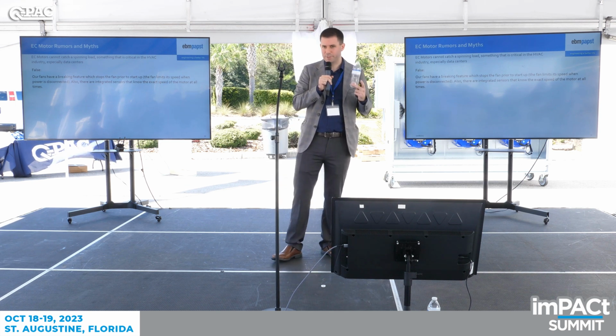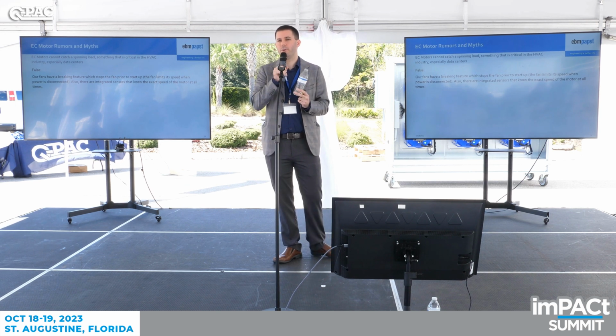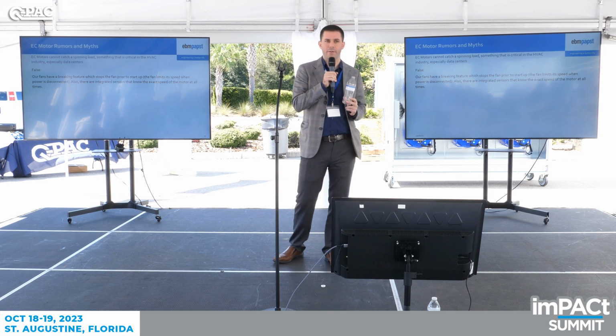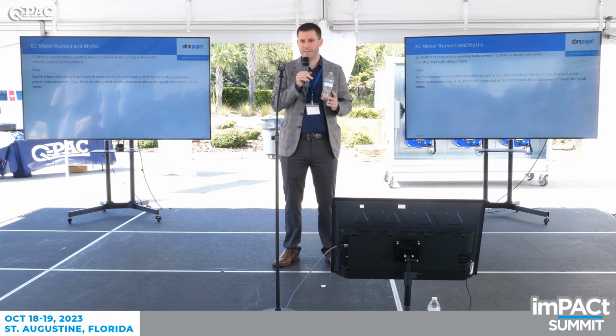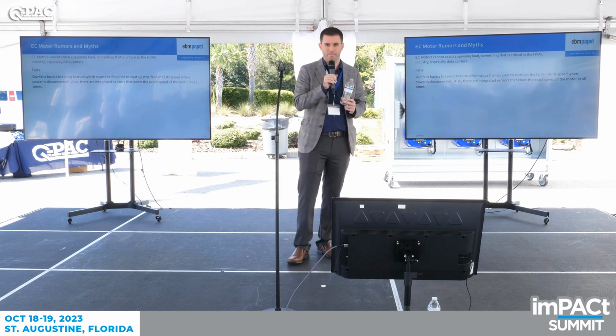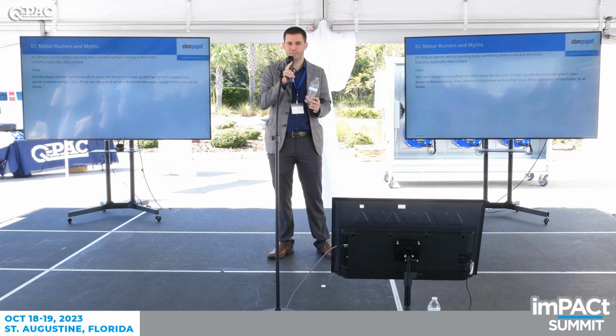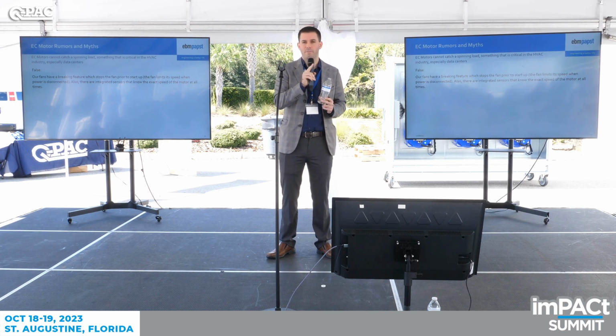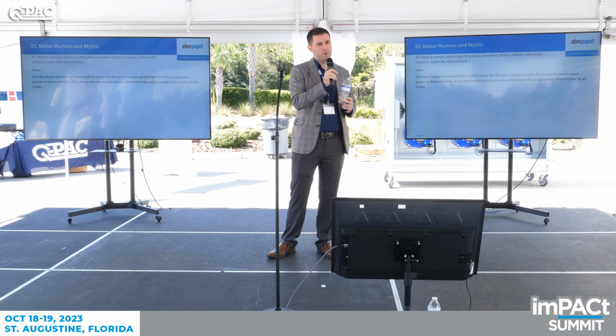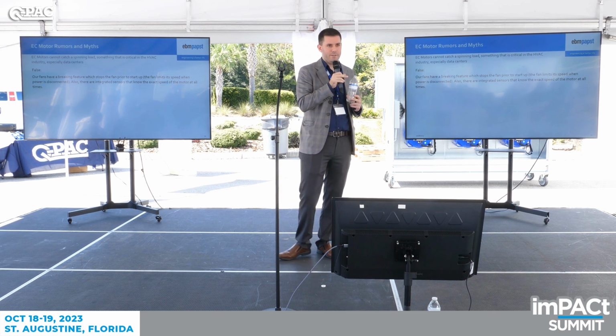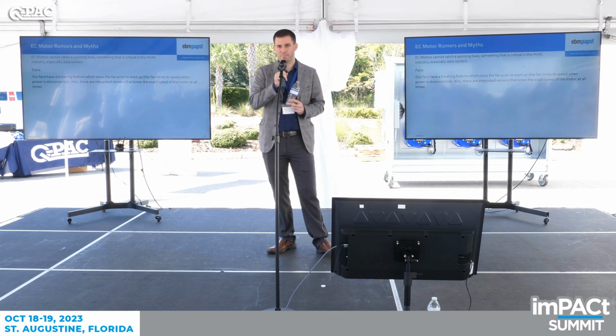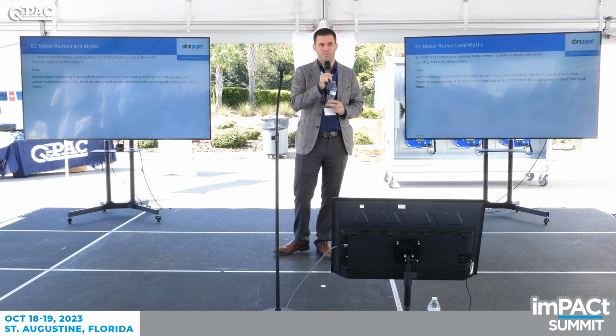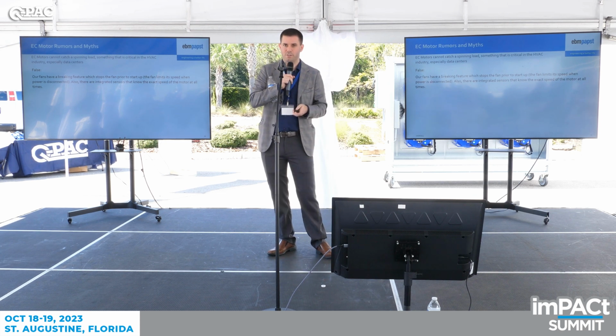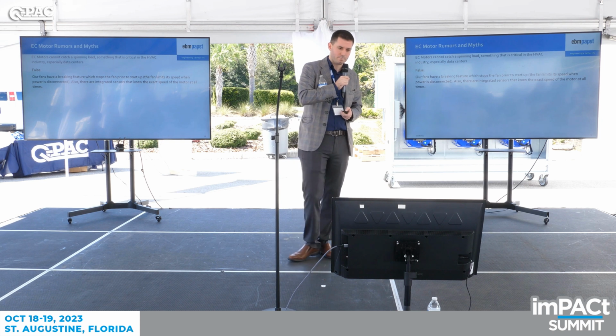And another thing that it will do is, say that the power left the fan and it starts spinning down, but it's not at rest yet, and power is restored. The EC fan will actually recognize what it's spinning at and ramp up from that point. So you don't have to worry about it over-ramping, overdriving, anything like that. The fan's pretty smart. It could tell you exactly where it was running and it knows exactly what to do to get back up to full speed.